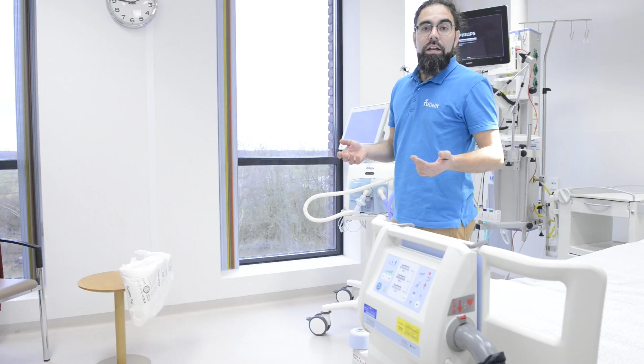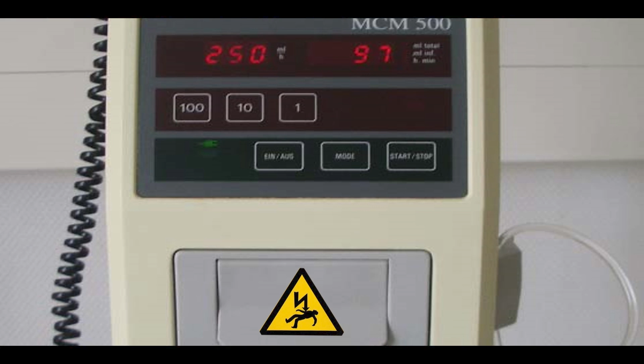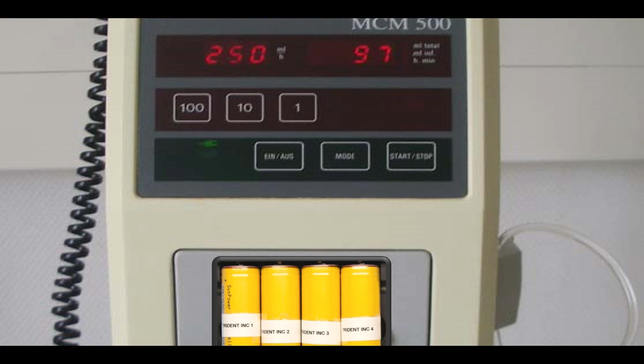For risk control of medical devices, we have these three types of measures. First, inherent safety by design and manufacture. This is the preferred way to go because inherent characteristics of the device are more likely to stay effective than an alarm or warning. With an inherently safe design, you could eliminate a hazard entirely, reduce the probability of the hazard leading to a harm, or reduce the severity of a harm. For example, by improving the safety of your device running on high voltage electrical mains power, not by just putting a warning label on it, but by changing its electronics to run on low voltage batteries instead of mains power.